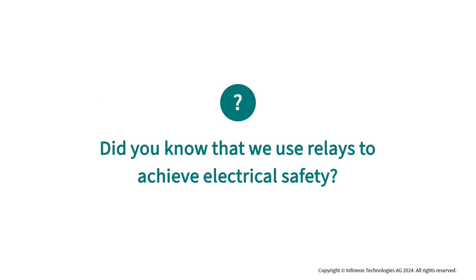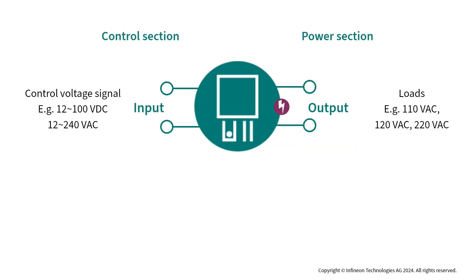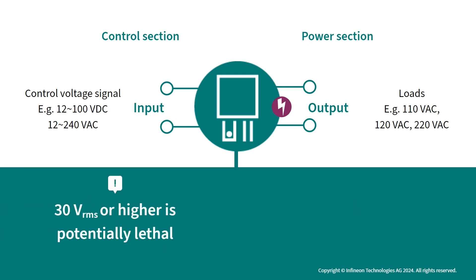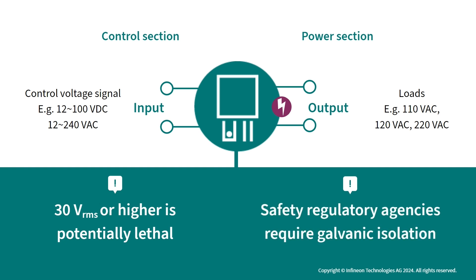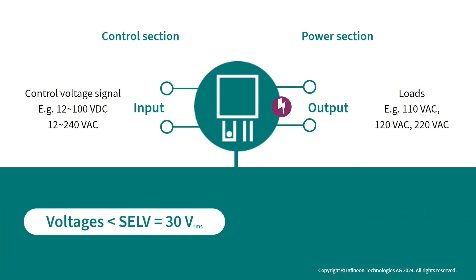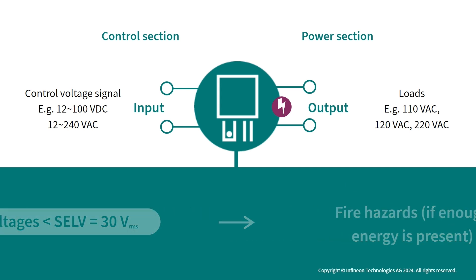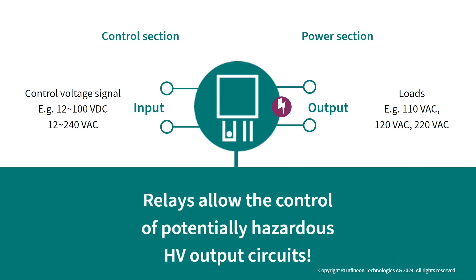We use relays to achieve electrical safety. High load voltages transferred onto logic can damage control circuitry. Additionally, 30 Vrms or higher is potentially lethal, and safety regulatory agencies such as UL, CSA, VDE, and BABT require galvanic isolation. A safe extra low voltage of 30 Vrms can also cause fire hazards if enough energy is present. With their safe low voltage input circuit and galvanic isolation, relays allow the control of potentially hazardous high voltage output circuits.